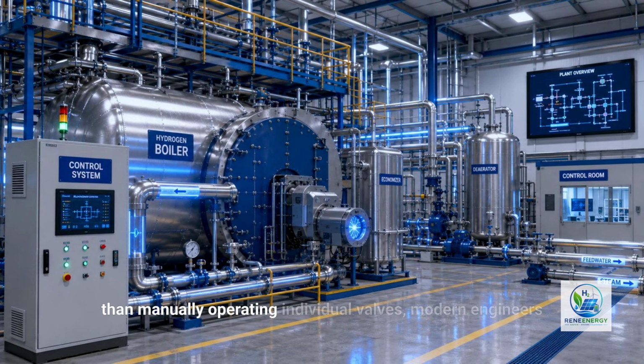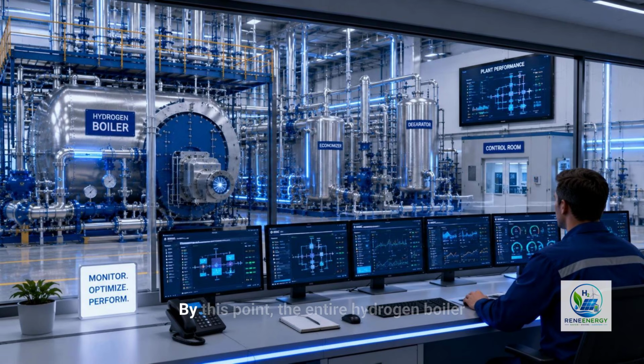Rather than manually operating individual valves, modern engineers supervise highly automated systems that can respond to changing process conditions in real time. By this point, the entire hydrogen boiler plant begins to come into focus. Hydrogen enters through the gas train, combustion releases thermal energy, heat is transferred into water, steam is generated and distributed to industrial processes, condensate returns for reuse, waste heat is recovered, and intelligent automation coordinates every step.